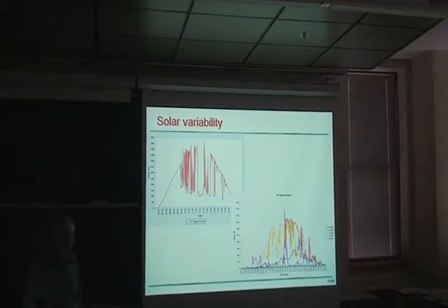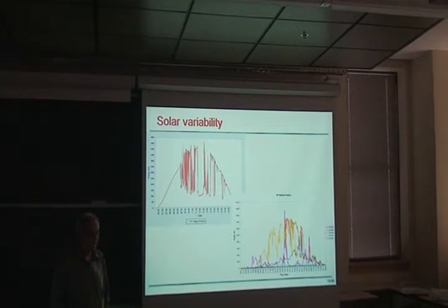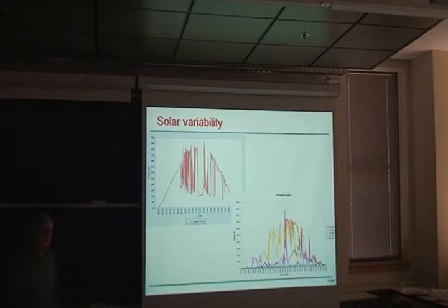Yeah. Now, is that just reflective of the infrastructure itself, the technology used, the design of the infrastructure? It is. Distribution networks are designed to be as cheap as possible because they have to span such a large area. You can certainly correct for it by putting in more voltage regulation equipment, or larger conductors for the distribution lines, but it all costs more.